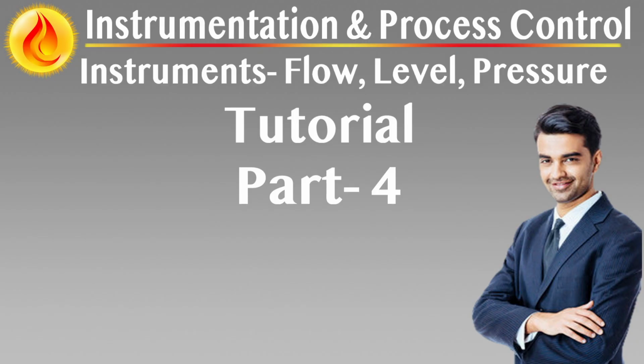Installation requirements and best practices. Flow accuracy depends heavily on correct installation. Maintain adequate straight-run piping upstream and downstream to stabilize the velocity profile. Avoid disturbances such as elbows, valves, or reducers directly upstream of the measurement point. Position the meter in a fully filled, non-aerated pipe for liquids and in non-condensing, debris-free gas lines. For vertical piping, upward flow is preferred for liquids to ensure the line remains full.